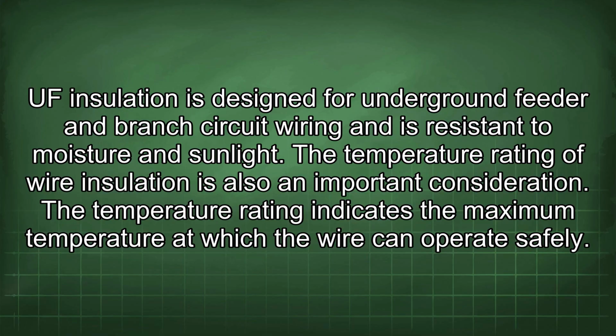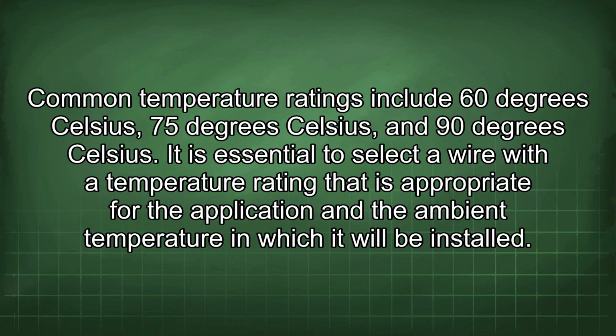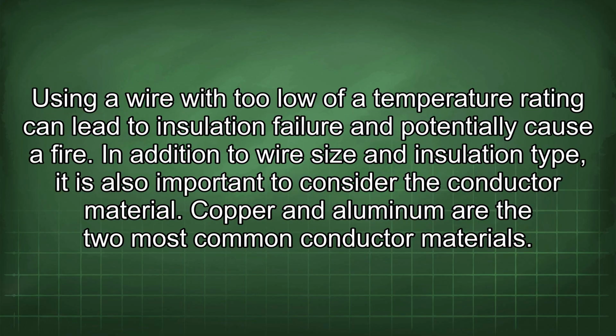The temperature rating of wire insulation is also an important consideration. The temperature rating indicates the maximum temperature at which the wire can operate safely. Common temperature ratings include 60 degrees Celsius, 75 degrees Celsius, and 90 degrees Celsius. It is essential to select a wire with a temperature rating that is appropriate for the application and the ambient temperature in which it will be installed. Using a wire with too low of a temperature rating can lead to insulation failure and potentially cause a fire.